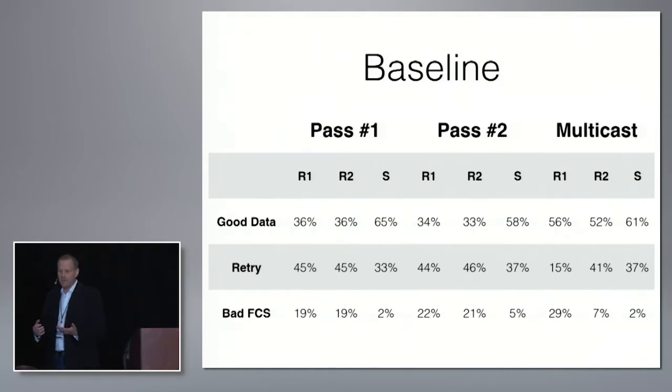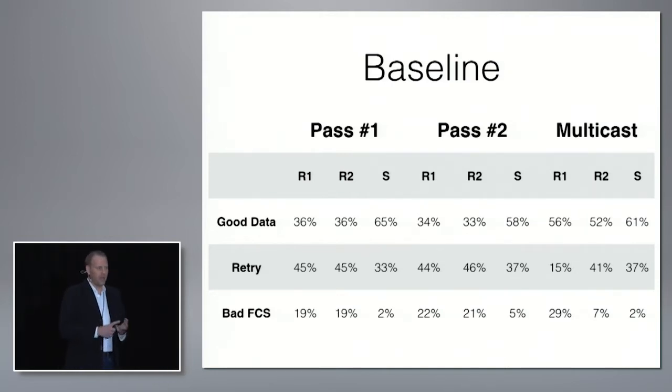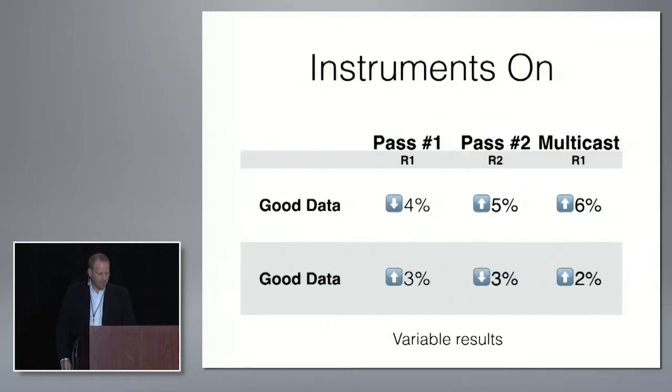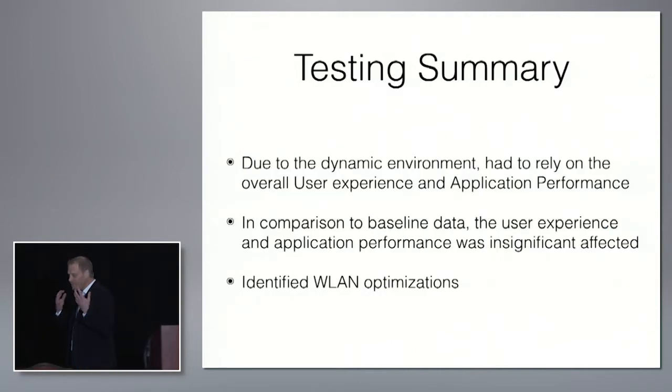So given this environment, this is a live environment. It's dynamic. You have equipment going in and out. You've got people going in and out, patients in and out, family members. You've got all kinds of things going on there. When we went to actually analyze the packets with the instruments on, we got all kinds of different things, quite honestly. So we had situations where things got a little bit worse. The good data got 4% worse, and in other passes it got better. And basically what we had to do, just as Devin had mentioned yesterday, is the user experience is king.